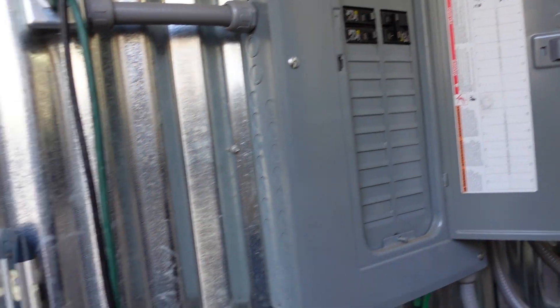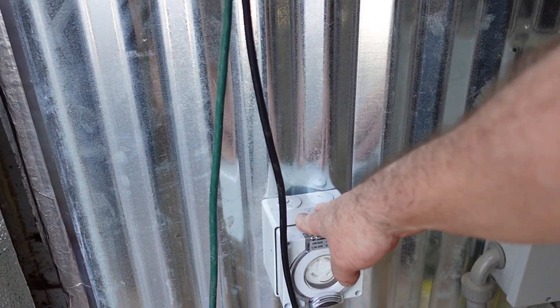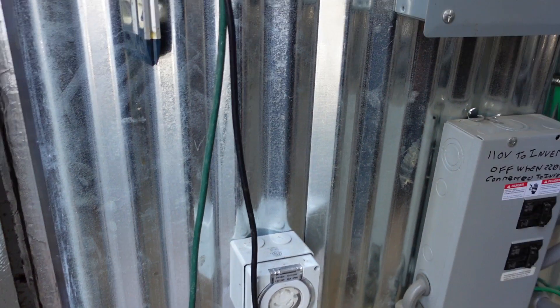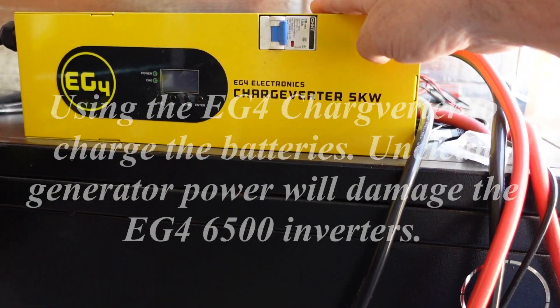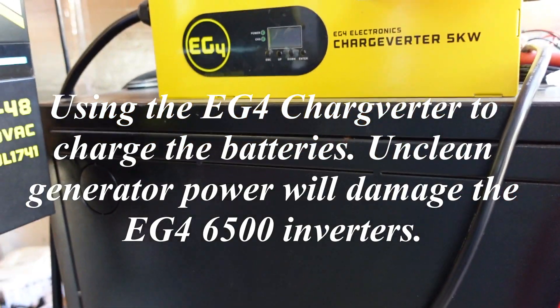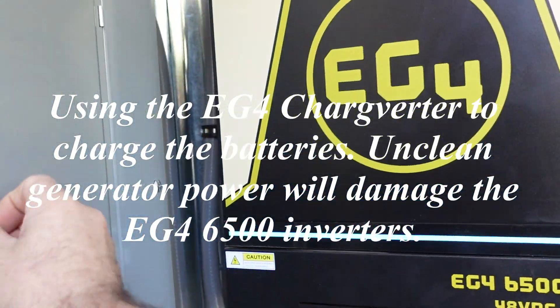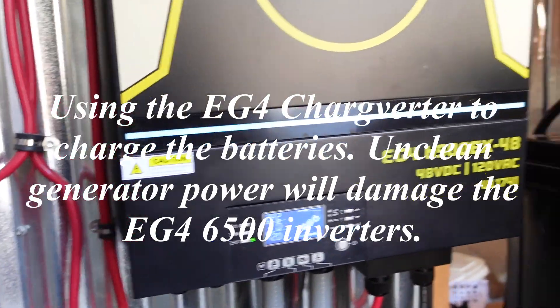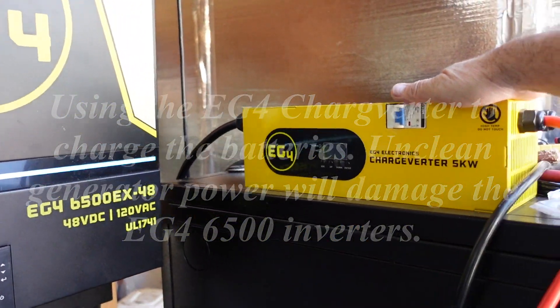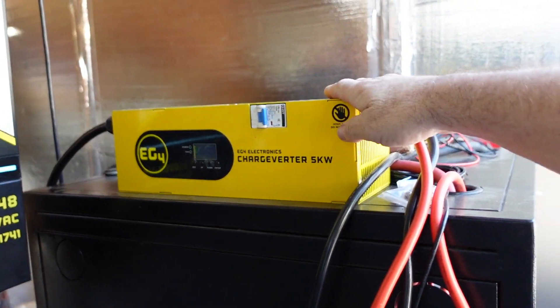One breaker goes to the camper and one goes to the electrical outlet out in the conex box. For the generator input, I have a 30-amp 220 plug, and we connect our EG4 Chargeverter. The reason we have a Chargeverter is because the way we're charging our batteries right now is using a generator. If that generator is producing unclean energy, it will destroy our batteries. So the EG4 Chargeverter takes our 220 power from the generator, converts it, and charges our batteries.